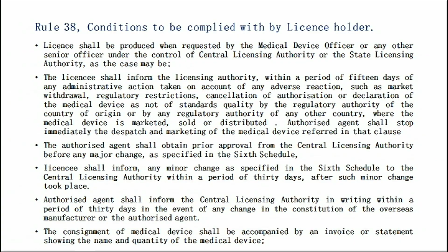The authorized agent shall obtain prior approval from the Central Licensing Authority before any major changes as specified in the 6th schedule. The licensee shall inform the Central Licensing Authority of any minor changes as specified in the 6th schedule within a period of 30 days after such minor changes took place. The authorized agent shall inform the Central Licensing Authority in writing within a period of 30 days in the event of any change in the constitution of the authorized agent or the constitution of the overseas manufacturer. Also, the consignment to be imported shall be accompanied by an invoice or a statement showing the name and quantity of the medical devices. So, these are the conditions of the import license which have to be complied with by the license holder.